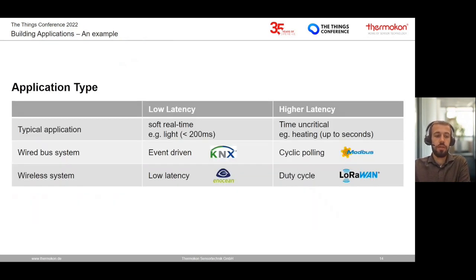these questions have to be answered before choosing the communication protocol. For example, if you're talking about different application types, some of them need a low latency time, such as soft real-time requirements for light control, since in building automation everything below 200 milliseconds is seen as real-time. That means you switch the button and the light switches on immediately. If you have these requirements, then an event-driven wired bus system like KNX, or a wireless system with low latency like EnOcean, is perfectly suited.